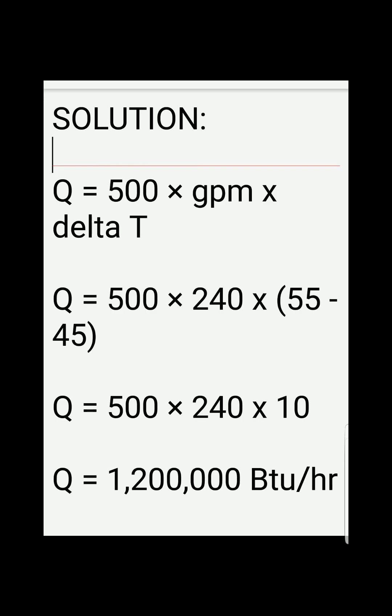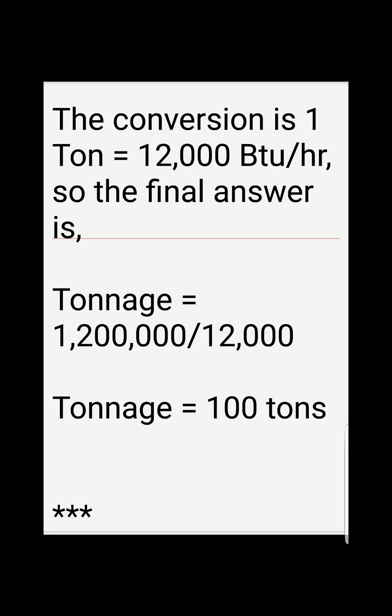Since we are asked about the cooling capacity in terms of tons or tonnage, we need to convert. The conversion factor is: one ton of refrigeration equals 12,000 BTU per hour. So the final answer is 1,200,000 divided by 12,000, which gives us 100 tons.